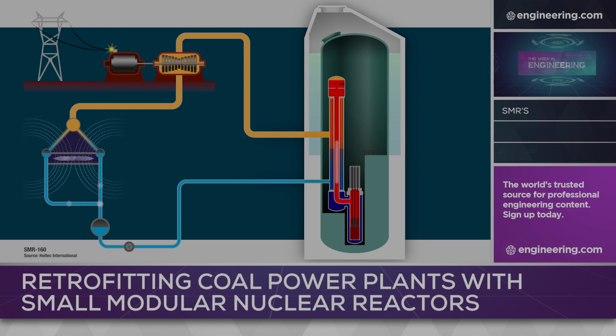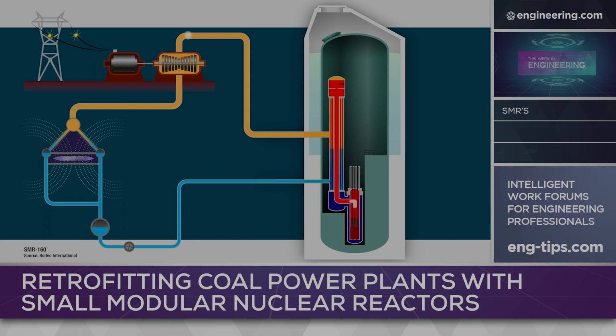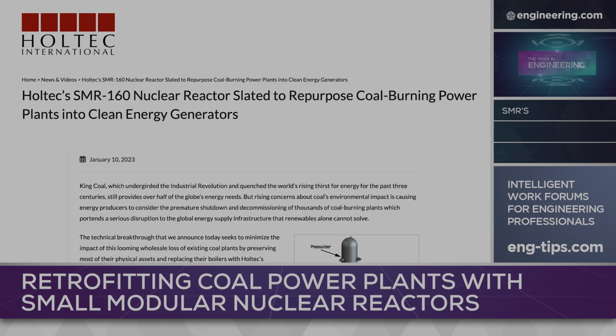This boosts the pressure and temperature of the low enthalpy steam delivered by the reactor itself. That steam is low in enthalpy by the standards of power generation, but it's still 700 psi at 595 degrees Fahrenheit. The additional pressure and temperature delivered by the compressor superheater add-on will deliver steam that can be tailor-made to replace coal-fired steam generating units at existing power plants.